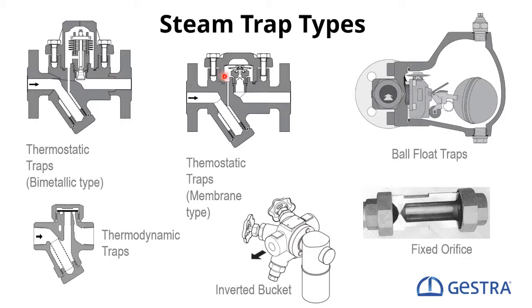The capsule type steam traps, working very fast, are very close to the saturation curve with only 10 Kelvin below, working the first years without any loss of live steam, but then, by the reaction time, it could happen that a small amount of steam is lost. If we look at the inverted bucket steam trap, we know we have a constant leakage, which is more or less 0.8 kilograms per hour. And if we look at the thermodynamic steam trap, we know they will increase in losing their live steam because of the leakage which happens in the seat area.